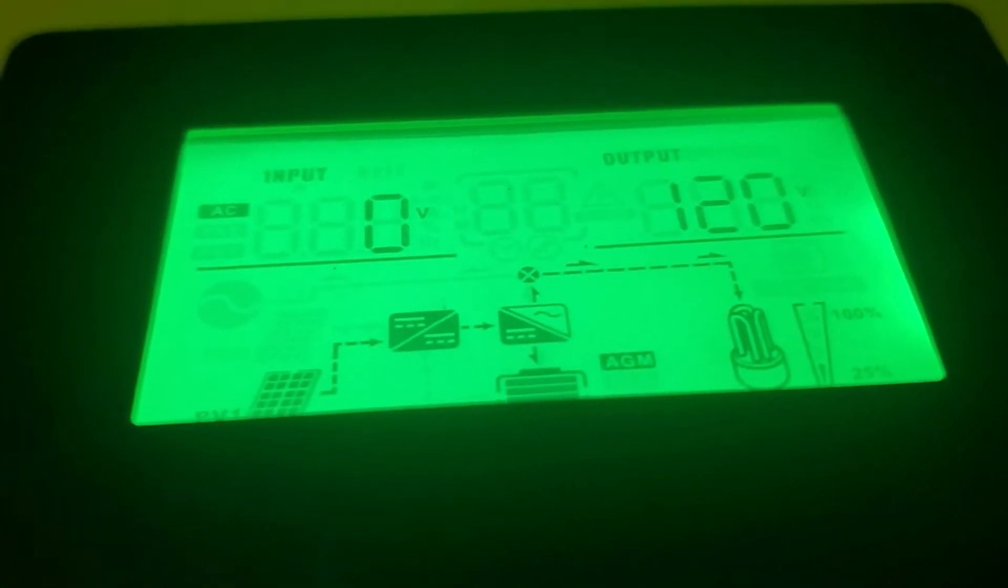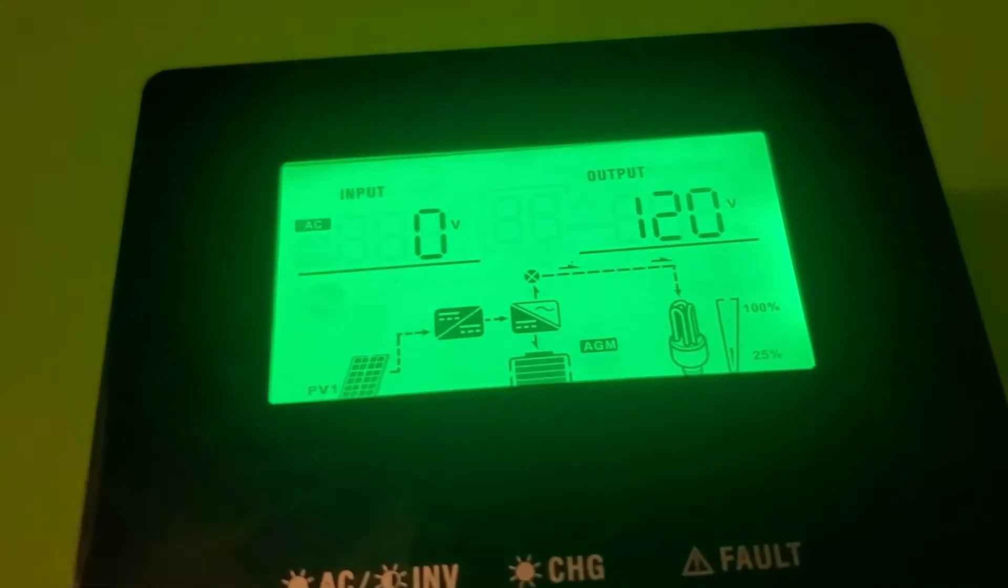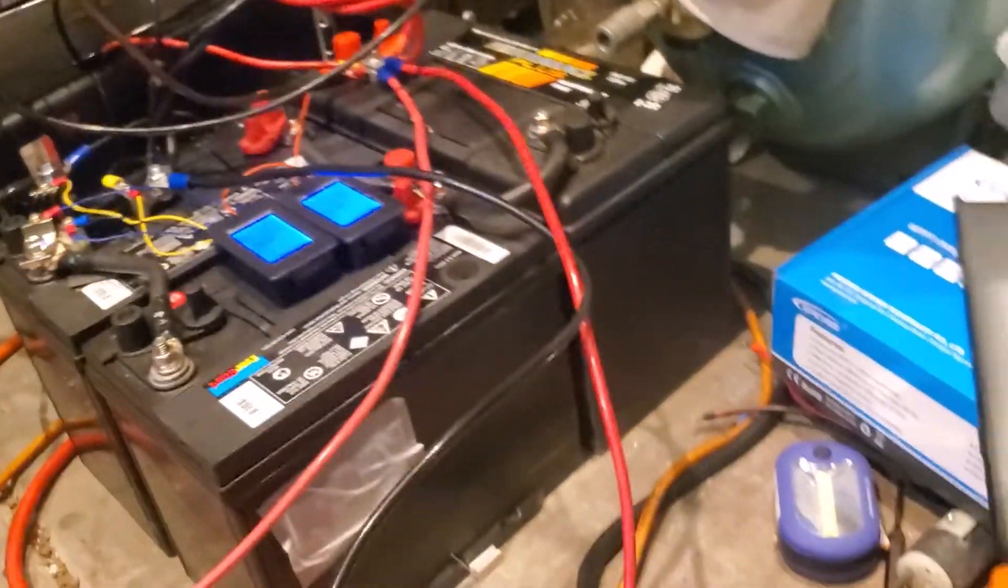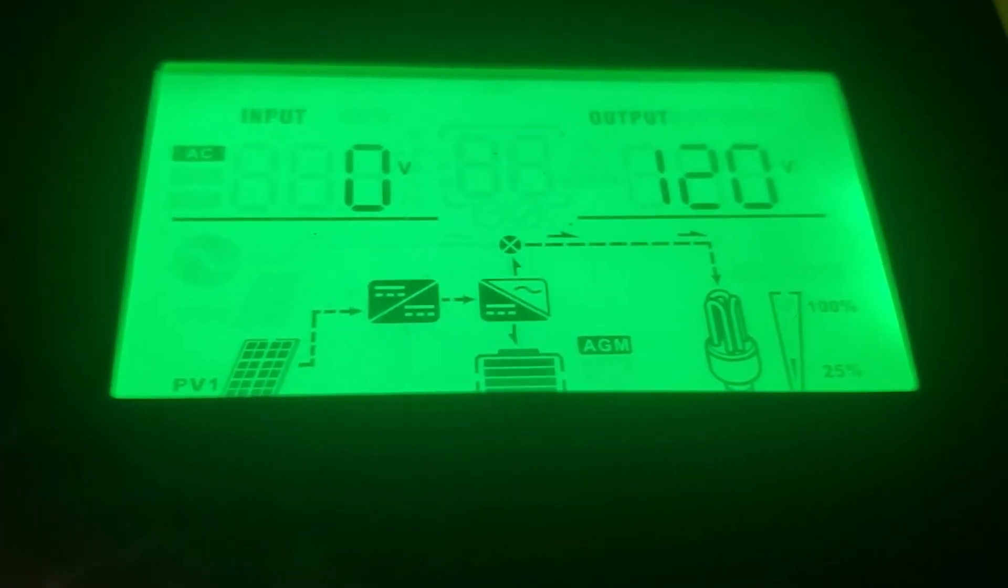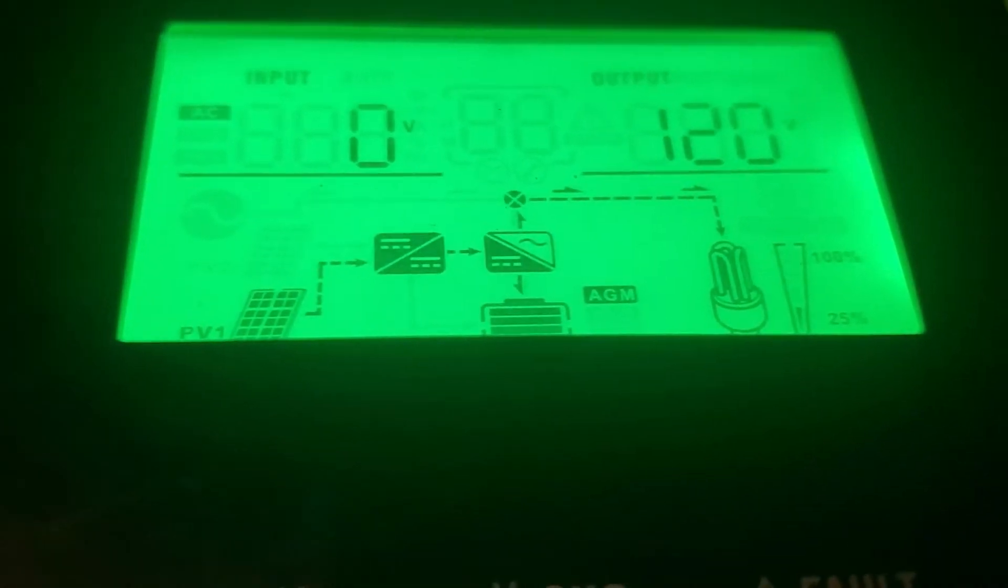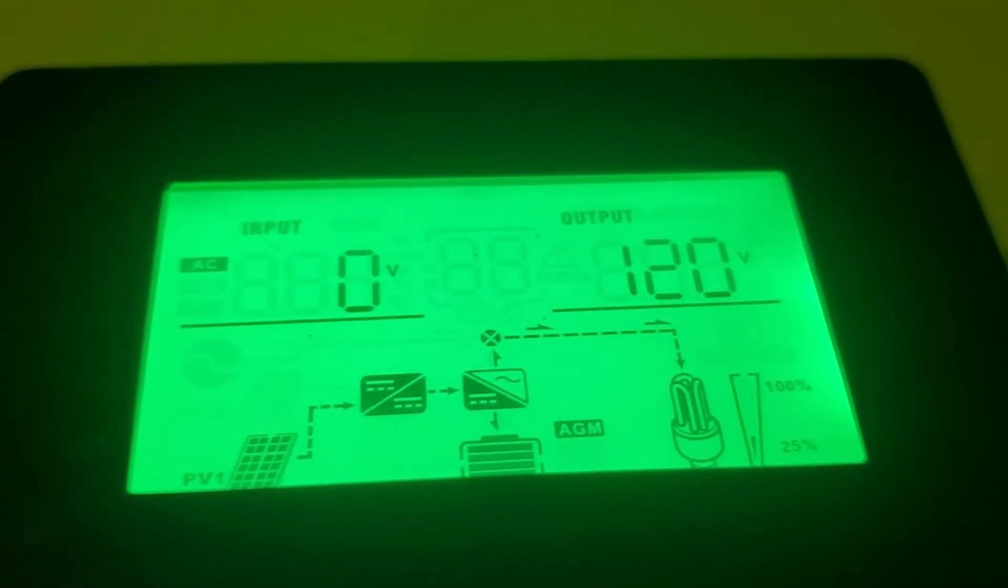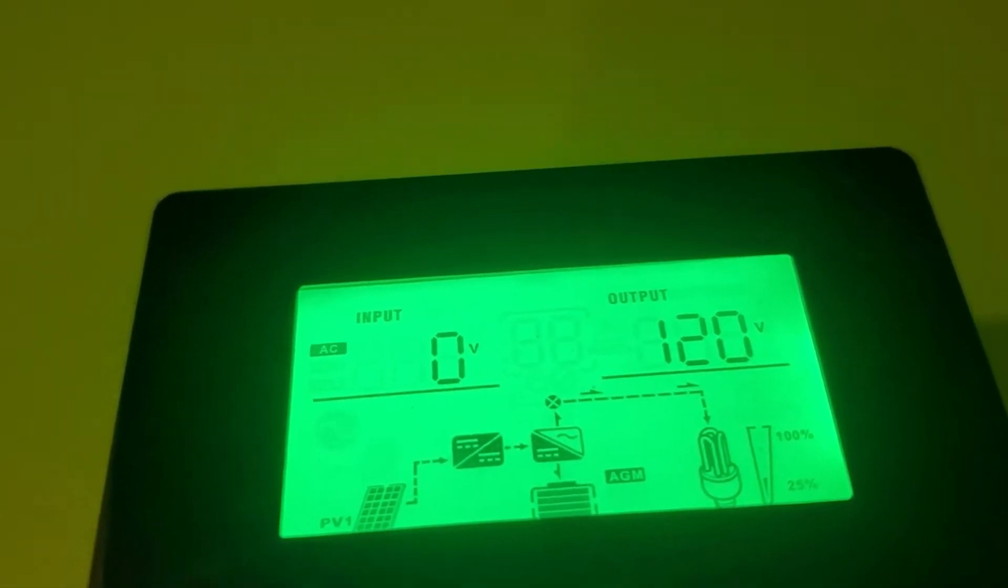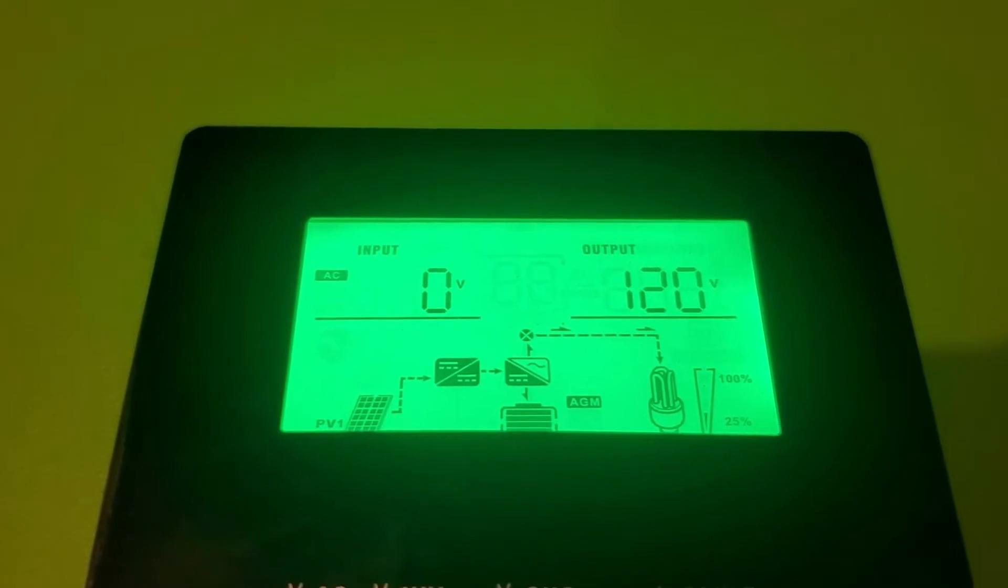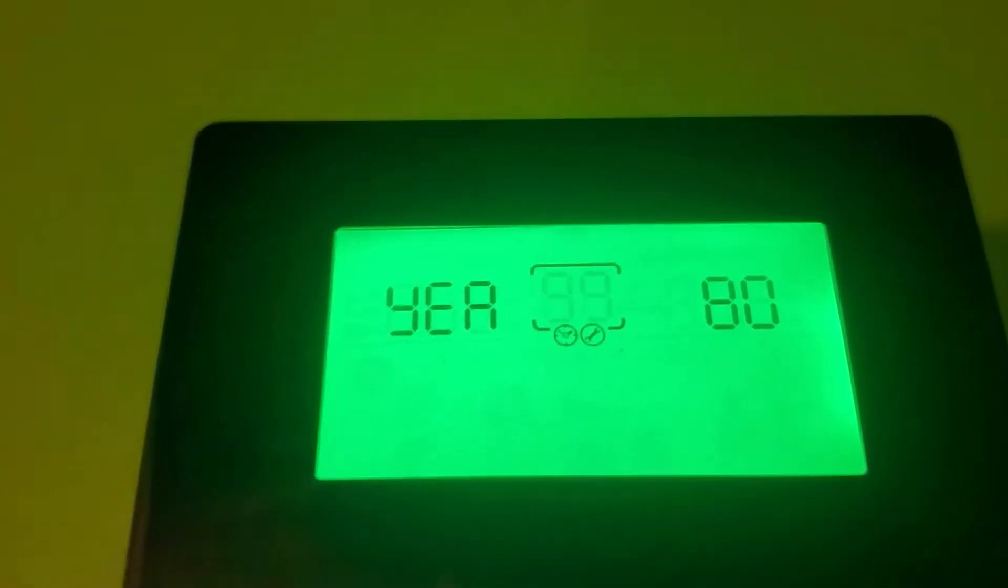It's possible the guy got rid of this because he thought something's wrong with it. He didn't read the manual. Let's take our Fluke over here and plug our terminals in here. 119.8, that is good enough for me. So I don't remember what else I need to change on here, but there's a few things and it won't really come into play until you plug in the other cord which will allow you to either charge your battery bank or it will allow you to use the utility as supply to your load, or you can have where it will load off of the solar first and then the battery, and then when it gets to a certain point it'll switch to utility or you can have it a bunch of different ways. And you can also grid tie this unit. So there's other parameters in here that we would need to change also. One would be the damn beep.